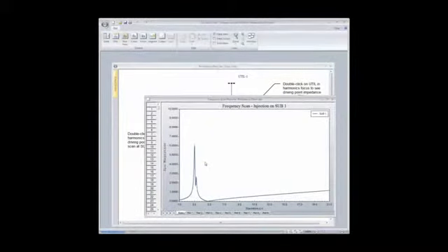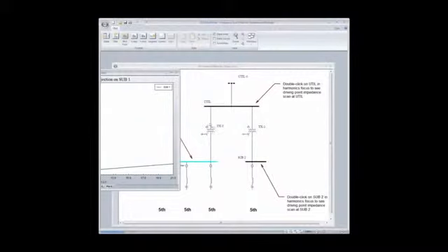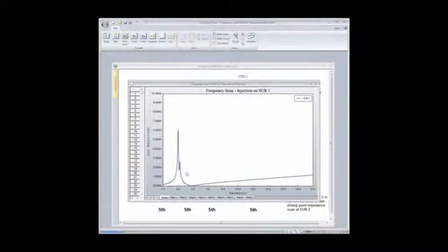The other filter on the other bus, looking up through the two transformers here. This transformer up and back down again is basically manifesting here. And so we have to be sure that when we're simulating our industrial systems, that we include every type of capacitive or filter component that might be involved somehow or linked into our system. So we can see that manifesting here.